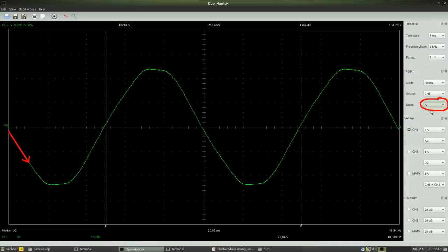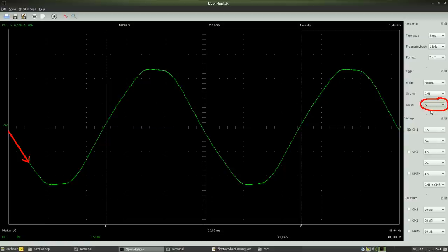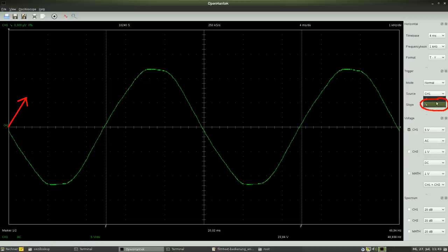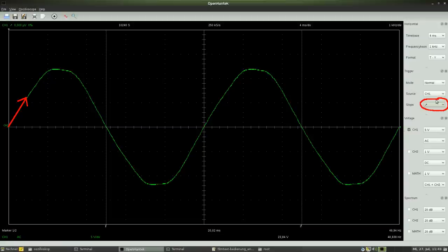Zero volt is adjusted again. The sine curve starts at the left edge with negative going voltage. When re-adjusting increasing slope, the curve starts with the positive going voltage again.